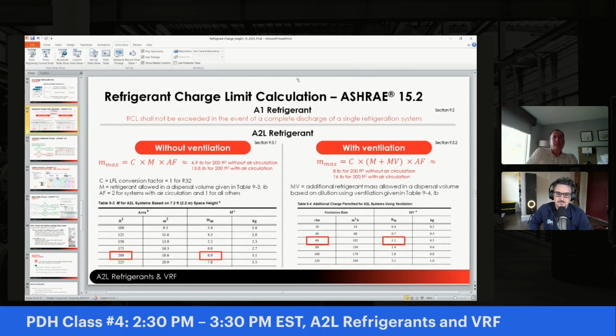So looking at this RCL limit for 15.2, here's another example. It's showing that without ventilation, your maximum charge for a room is calculated as the refrigerant charge from the table times your refrigerant conversion factor times your air circulation factor. The refrigerant conversion factor for R32 is 1. That's your C variable. And again, don't try to think too hard about this stuff, because we've made it so you don't need to worry about it too much. Air circulation factor is 2 for systems with air circulation and 1 for others. So in this example, roughly 7 pounds of refrigerant is allowed for a 200 square foot space without air circulation. And if you have air circulation, you can have up to 13.8 pounds. So big difference there.